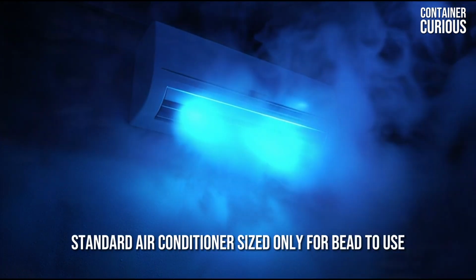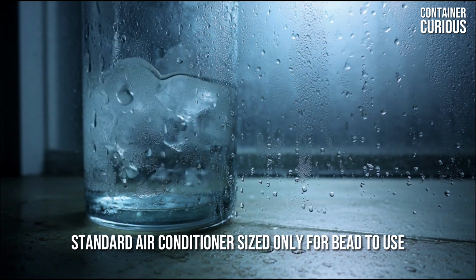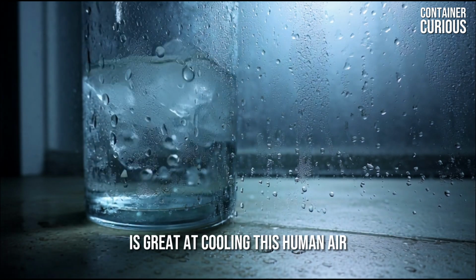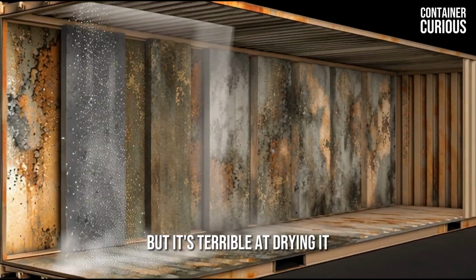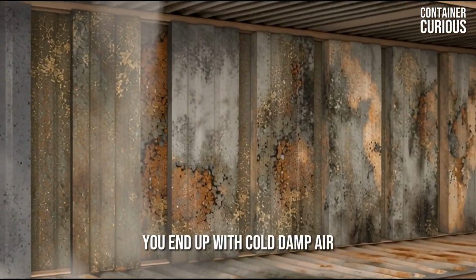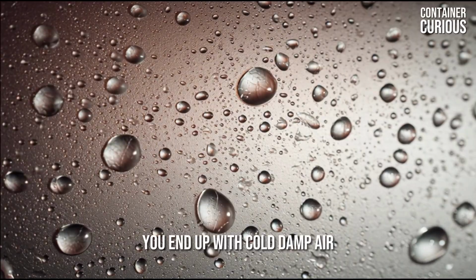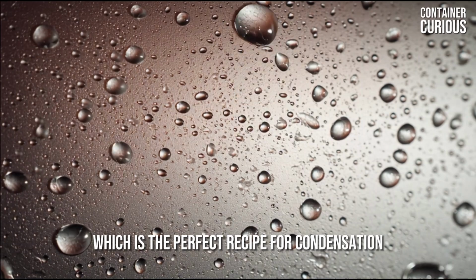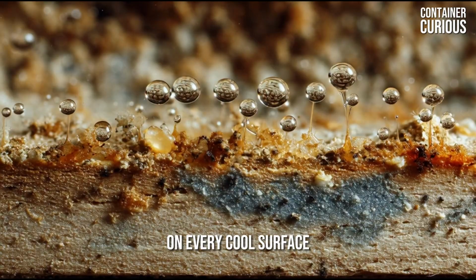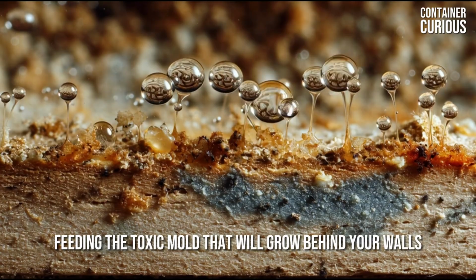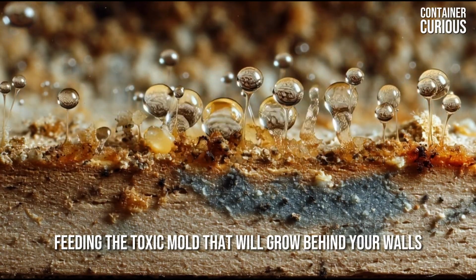A standard air conditioner, sized only for BTUs, is great at cooling this humid air, but it's terrible at drying it. You end up with cold, damp air, which is the perfect recipe for condensation on every cool surface, feeding the toxic mold that will grow behind your walls.